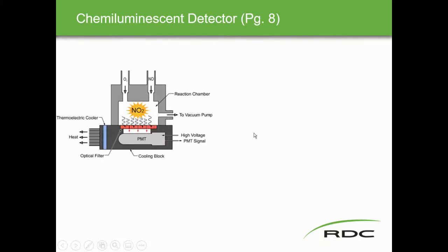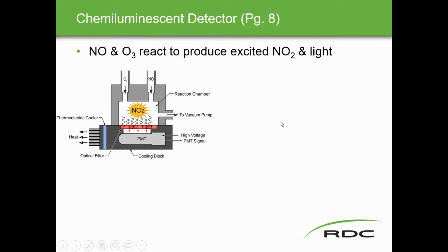The detector — the photomultiplying tube — has a cooling block and an optical filter. The NO2 and emitted light enter here. The reason it is cooled is to eliminate heat and reduce electrical noise. A high voltage is applied, and then the signal comes out. The cooling block acts as a heat sink. Any excess O3 ozone goes out to the vacuum pump.